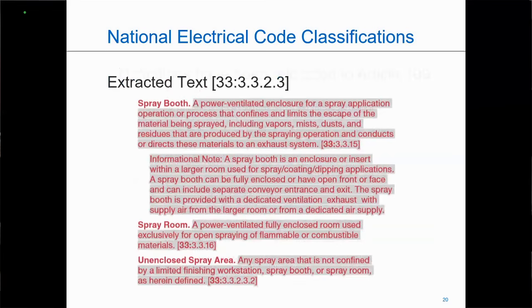So Article 516 uses a lot of extracted text. They do a lot of extracts from NFPA 33. So when you see brackets, that is actually extracted text that's being used in those particular areas. That extracted text is taken word for word. So in the particular case in 2017, when you saw a lot of those changes, it wasn't that Code Making Panel 14 decided to do a lot of changes, but the people of NFPA 33 had made numerous changes. And since it was extracted text, Code Making Panel 14 had to take it word for word and put that into Article 516.